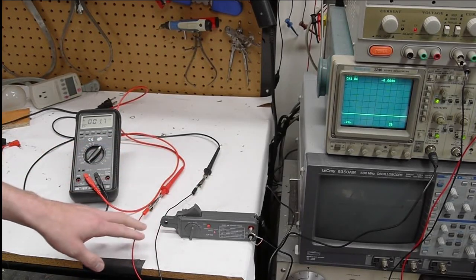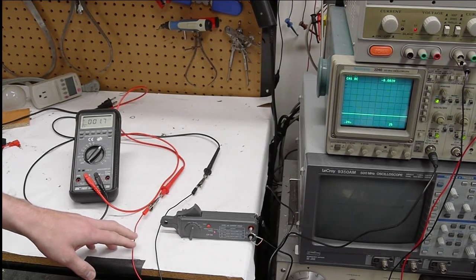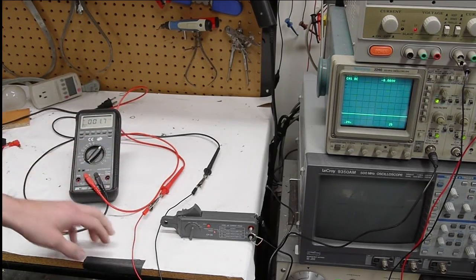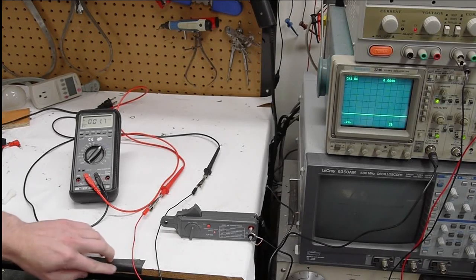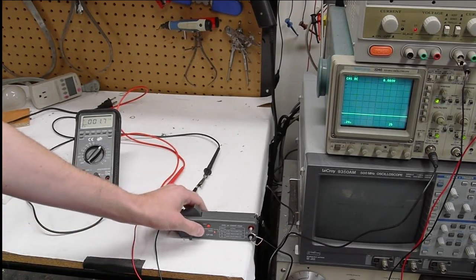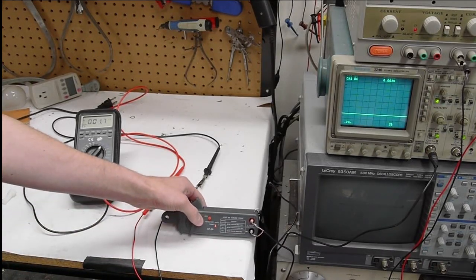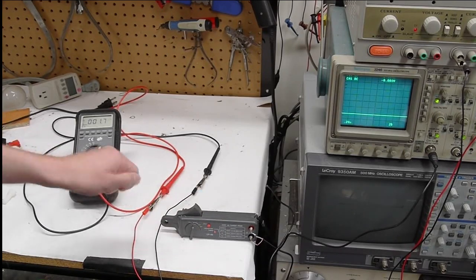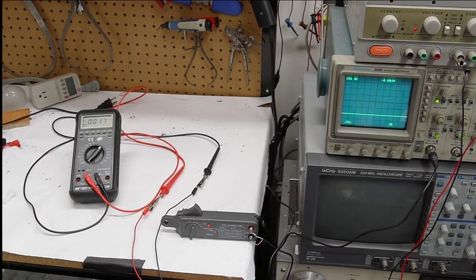So the problem with the Hall effect sensors is that they're sensitive to outside magnetic fields, even the Earth's magnetic field if you're measuring small currents. So the DC probes all have a zeroing button, or a zeroing dial, so that you can make sure to get a zero reading before actually measuring the current that you want to measure.